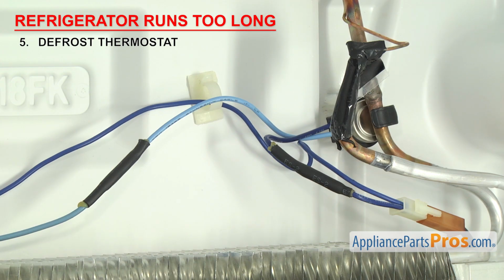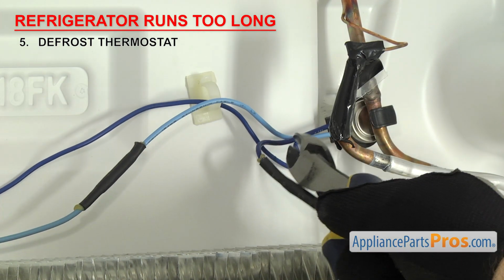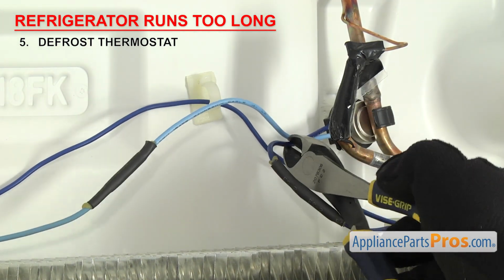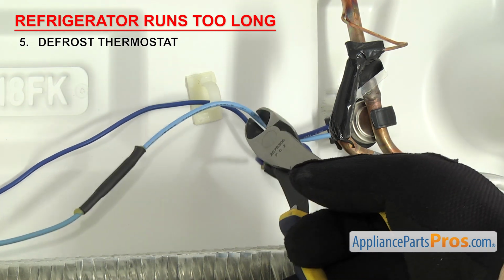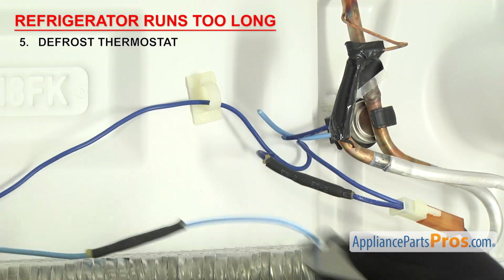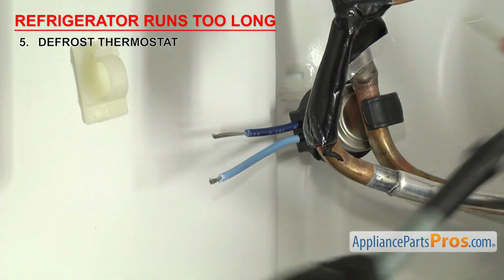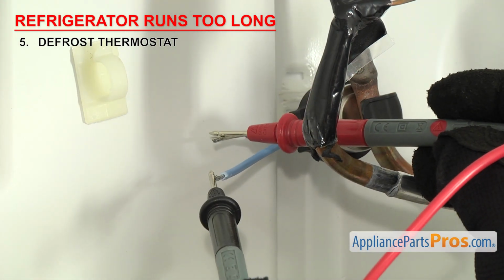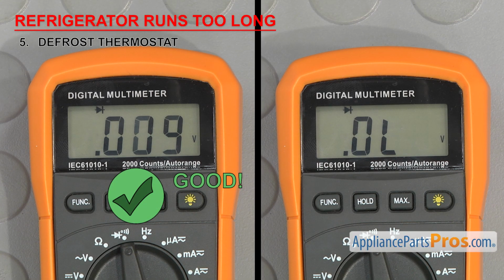Depending upon your design, you may just have to unplug the wiring harness and touch a probe to each terminal. If not, you would have to cut the wires to make sure the thermostat is removed from the system and then test each wire. Touch a probe to each terminal or wire. If the thermostat has continuity when it's cold, then it's fine and you can splice and seal it back in. If it doesn't, then it's failed and needs to be replaced.